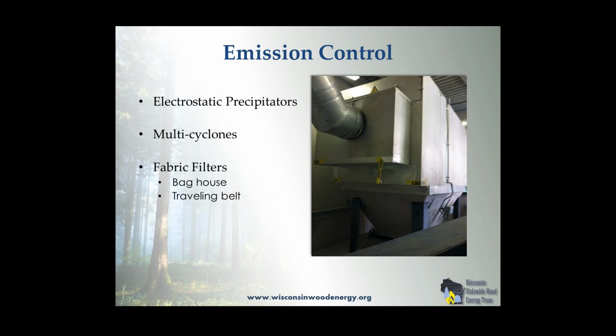And fabric filters can be just as effective as electrostatic precipitators. They tend to be a little more energy inefficient than electrostatic precipitators in that the pressure drop through the baghouse is usually greater than through the ESP. An ESP takes some energy to run, to energize the plates, but it's not comparable to the amount of horsepower required for the pressure drop across a baghouse.